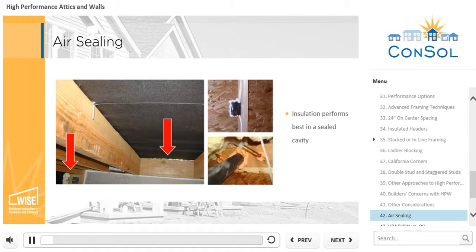Insulation performs best in a sealed cavity. If the house isn't properly sealed, cold can easily transfer through the rafters and studs, and, in some cases, condensation can form in the drywall. Wall stud cavities should be sealed to provide a substantially airtight envelope. Plumbing and wiring and other penetrations through top or bottom plates or exterior sheathing should be sealed, and minimally expansive foam should be used to seal all gaps in the air barrier. When combined properly, air sealing and insulation work well together to stop heated and cooled air from escaping the building envelope.